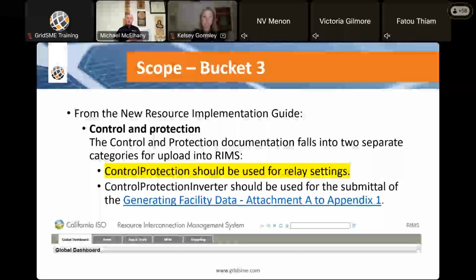I'm not going to spend any slides on that particular piece. That is a piece that I and other engineers will look through to make sure that the settings for the particular voltage and frequency tripping do not violate PRC 24 or the other fault ride through components. But the main focus is going to be on the control protection inverter settings report and the attachment A, the full. That's why we always get confused on saying attachment versus appendix, because it's attachment A to Appendix 1. And here we are today talking about Appendix H.